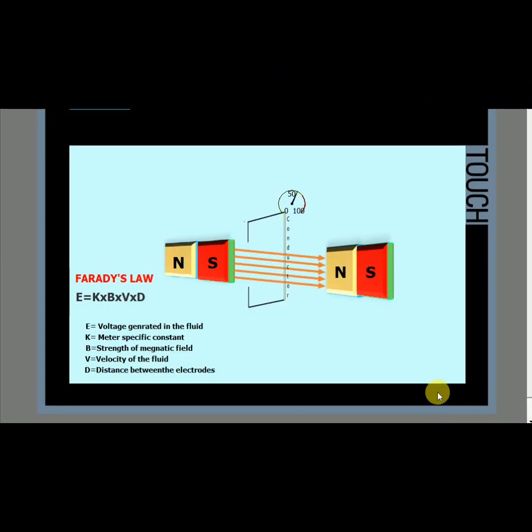Faraday's law. In 1831, Michael Faraday observed that a voltage is induced across any conductor as it moves at right angles through a magnetic field and that the voltage is proportional to the velocity of that conductor. This is called Faraday's law of electromagnetic induction. To generate a voltage according to Faraday's law, we must have a moving conductor. What is the conductor in our flow application?